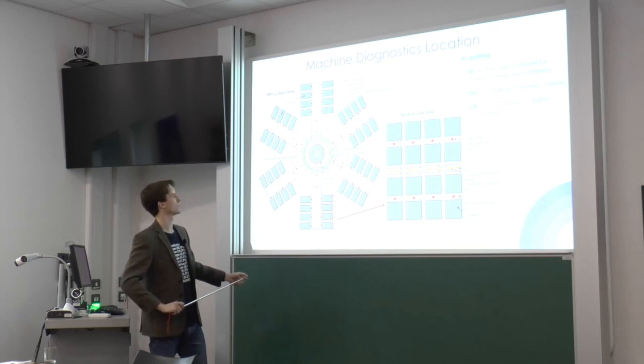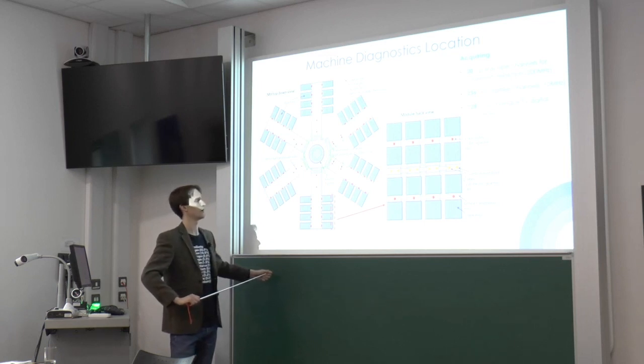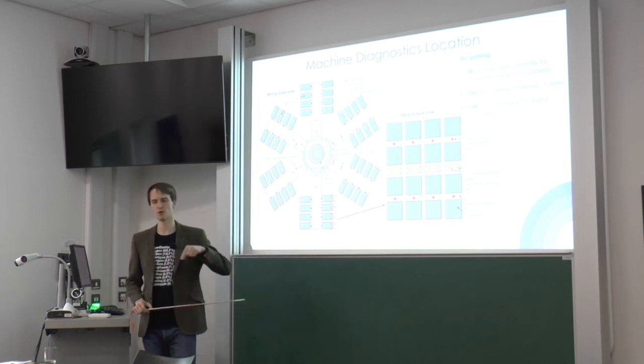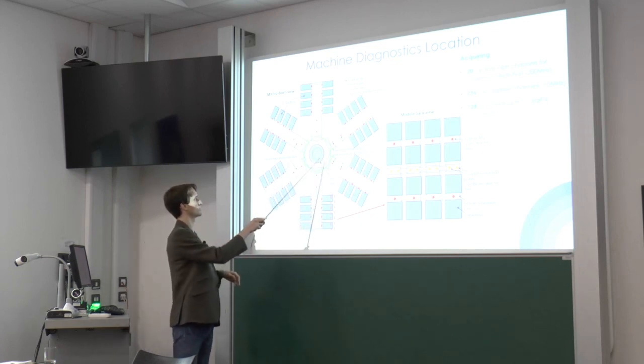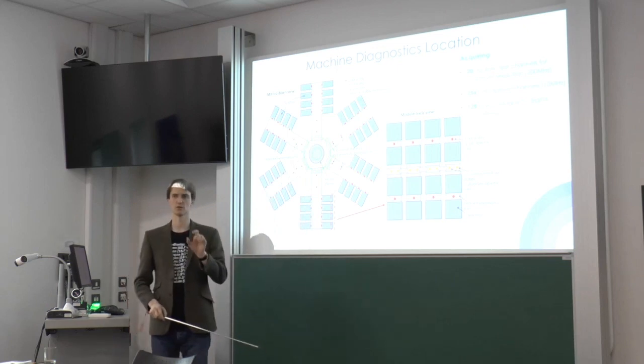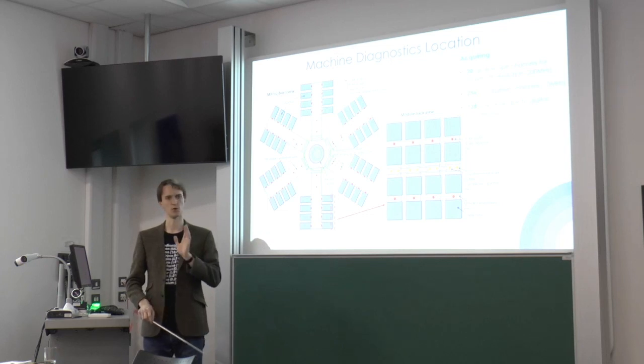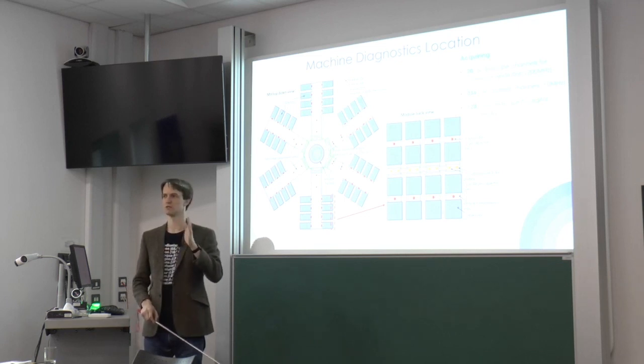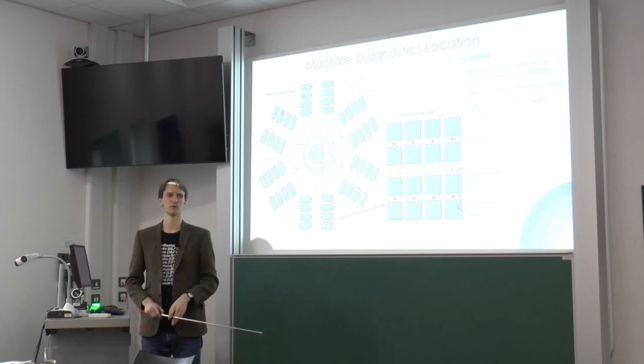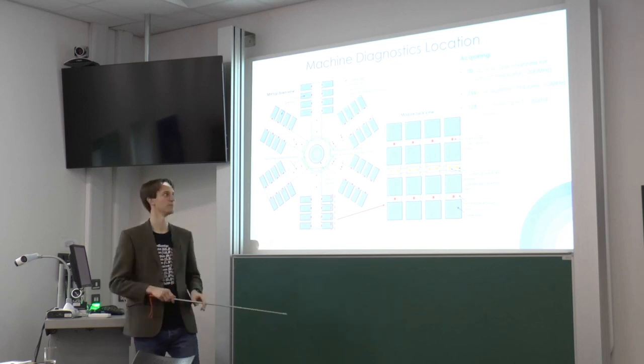And then to give us our most reliable current measurement, we have some Faraday lines. These are fiber optics which are looped around the important conductors. We have one per module, and then we have a total current measurement with a special fiber. Basically you put a polarized laser down this fiber, and when the fiber is in a magnetic field, it causes the polarization to rotate, and you measure the rotation of the polarization. It gives you a direct measurement of the magnetic field, which you can then convert to current.